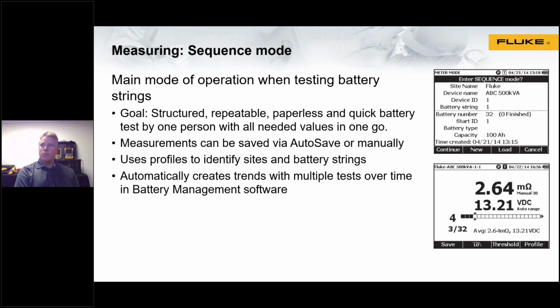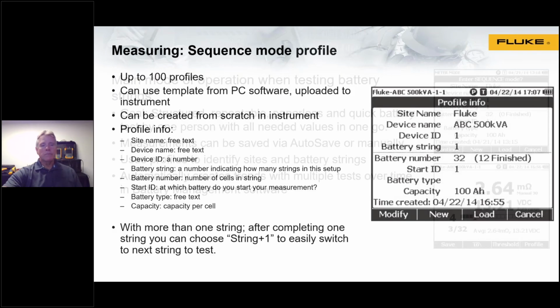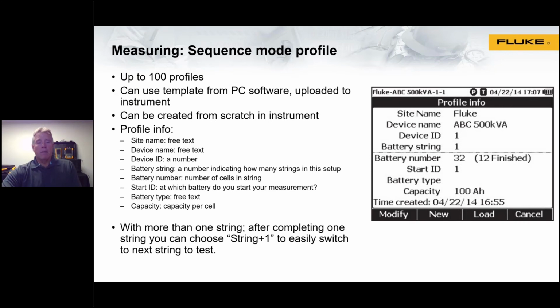The idea is to have these sequences preloaded, pre-programmed in the tool, just make the measurements, save the readings, and then get that information out to the software to be able to look at those trends over time. Up to 100 profiles can be stored inside the tool. Again, we can create the profiles either in the tool itself, or you can create a template in the PC software and load it into the instrument. So all the different attributes, site names, device names, battery string numbers, you can use any or all of these in order to make measurements.